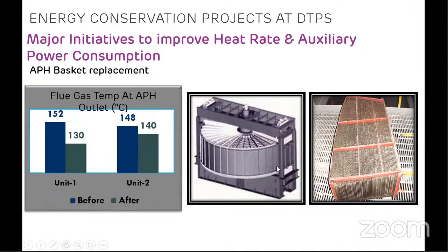Then, as you may be aware, we have an air preheater in our plant. It's a coal-based thermal power plant, so we have an air preheater. This air preheater consists of baskets. The flue gas temperature is monitored at the inlet and outlet of the APH. If the flue gas temperature at the outlet is higher, it means that the heat recovery from flue gases is poor. If the flue gas temperature at the outlet is lower, it means that the PA and FD are gaining more heat from the flue gases. Heat exchange is very good, so the APH is working very efficiently. So we monitor the flue gas temperature at the APH outlet.